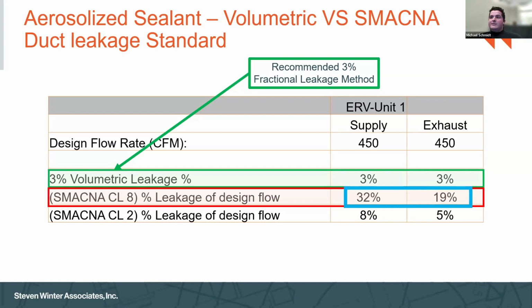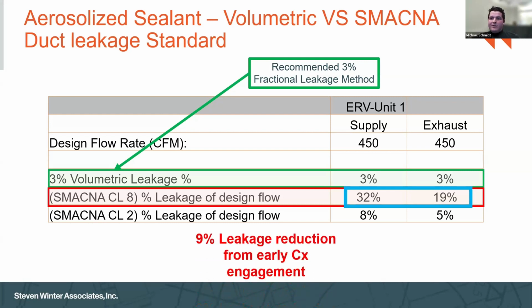What's the other problem here is that the SMACNA standard is based on the actual square footage of the ductwork, the physical area of that ductwork. And in this case, there were significantly different square footages of ductwork. So there was more supply ductwork in physical area than exhaust. And what that ends up with is an imbalance right off the bat, right? Here we had 32% leakage on supply, 19% at exhaust. So how is the balancer supposed to come in and meet the passive house requirement, balancing these air streams within 10%, when it's already starting at a disadvantage? One last note: we were involved early on this project, and were able to reduce leakage during construction by about 9% throughout this engagement with our passive house team and our commissioning agent.